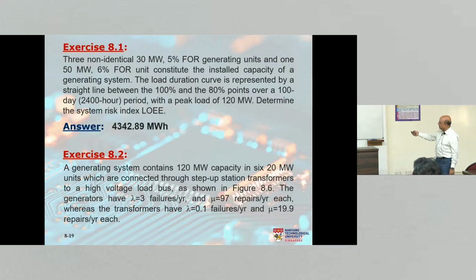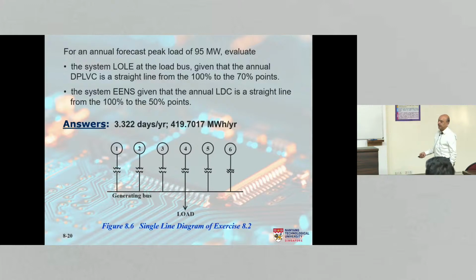The generators have a failure rate of 3 failures per year and 97 repairs per year, whereas the transformers have a failure rate of 0.1 failures per year and a repair rate of 19.9 repairs per year. Notice the difference between the repair rates of the generators and transformers. You should be convinced, especially those working in the industry, that a transformer needs much longer to repair, right? So the repair rate cannot be very high. You can't repair a transformer 500 times in a year. It takes much longer, sometimes weeks, to repair a transformer. Okay? So this is a very practical question.